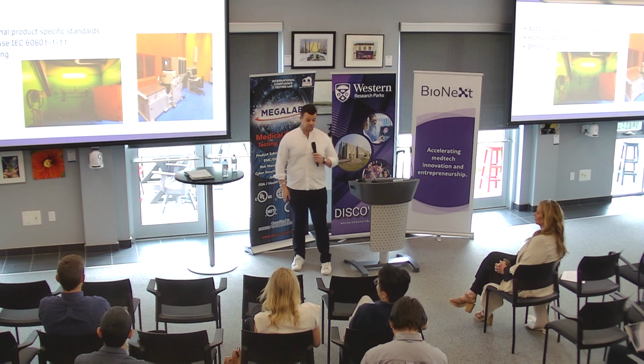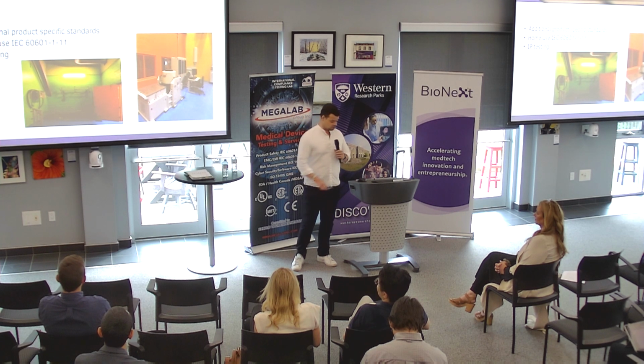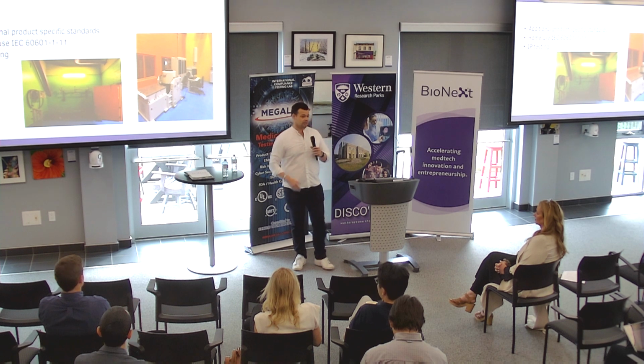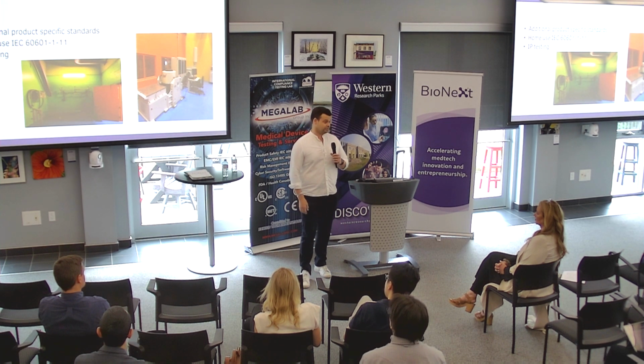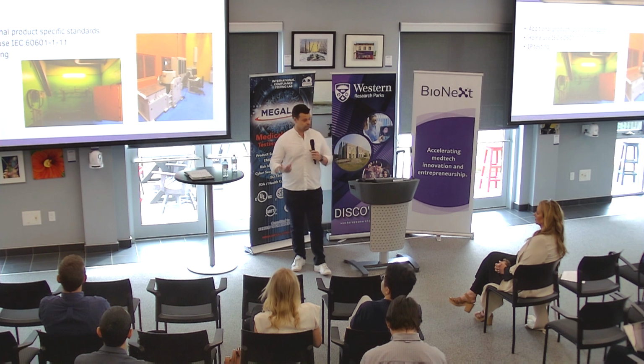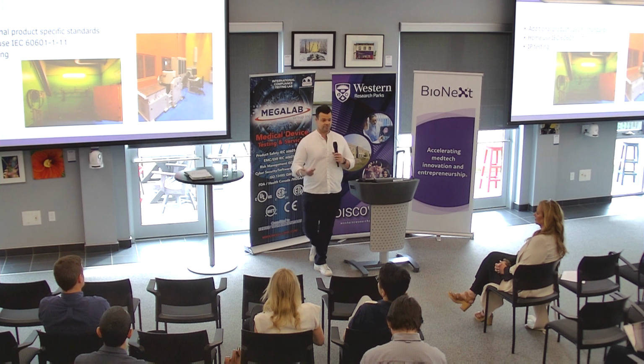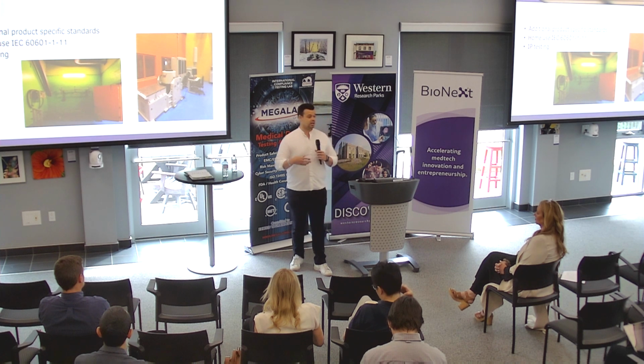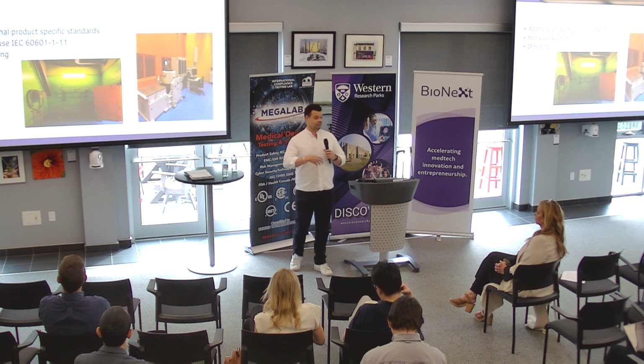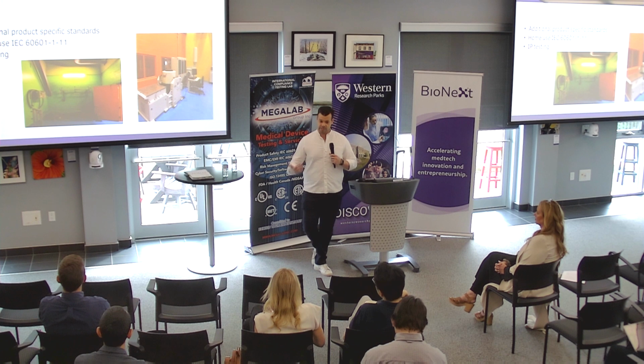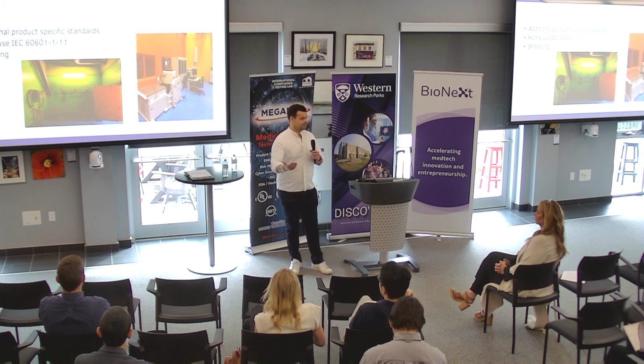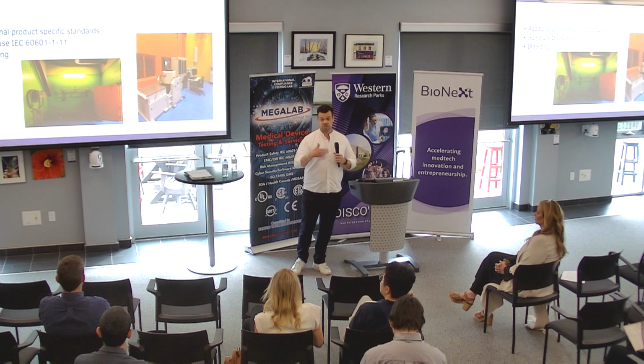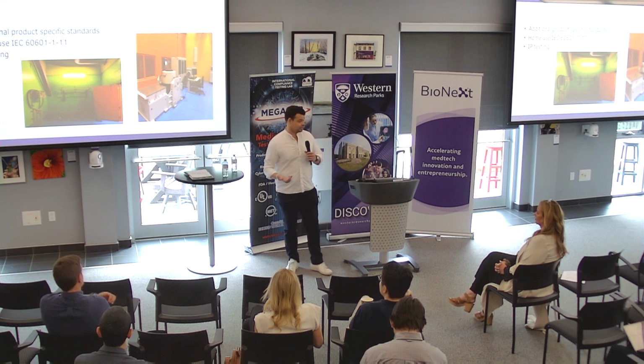So when I mentioned that standard IEC 60601, there's also all kinds of other little headers that go under that. Like you've probably heard the term risk management before. So there's ISO 14971, which is for risk management. Part of your submission to the FDA, you have to have a risk management file. Our job is to review that file thoroughly and be really picky, so that when you do submit it, someone doesn't come back and delay your application because someone wasn't picky enough on your risk management file.